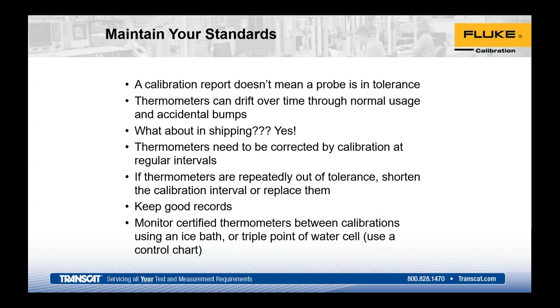The best method to prevent that is a triple point of water, but you can also use a really good ice bath in a dewar. This is just really good, cheap insurance to write into any QA process: you're going to check your standard at 0 periodically. And again, this is going to have to be defined by your quality folks typically, and it's usually a result of risk versus recall. So this one shows a triple point of water. They're going to get you the best repeatability, but a good ice bath in a dewar also nets you really good uncertainties, if it's built properly with distilled water, distilled ice, you crush it well and allow it to stabilize. They work really good. And again, really cheap insurance to take a few minutes every few weeks to check your unit.